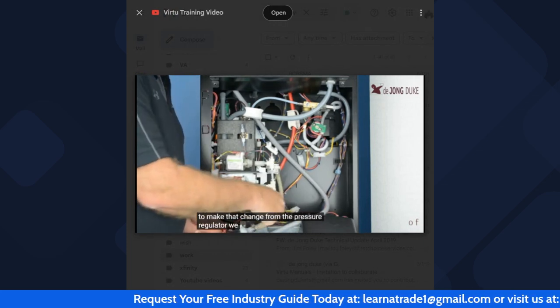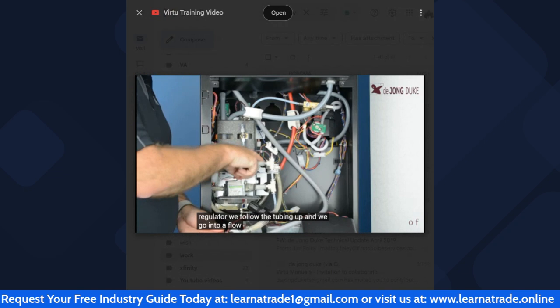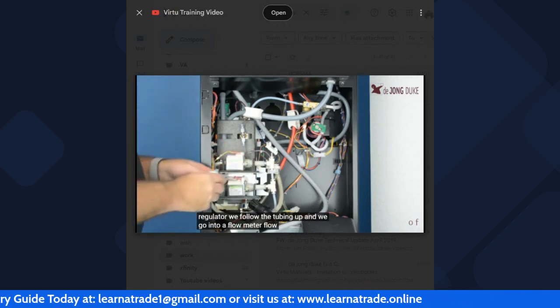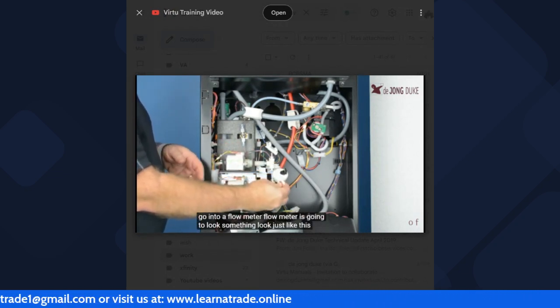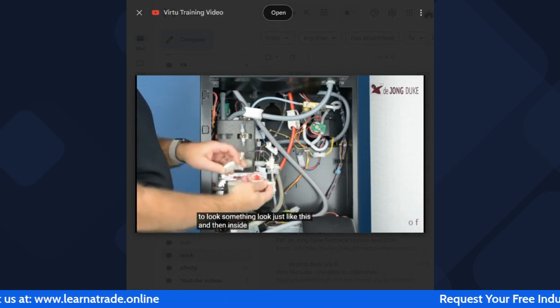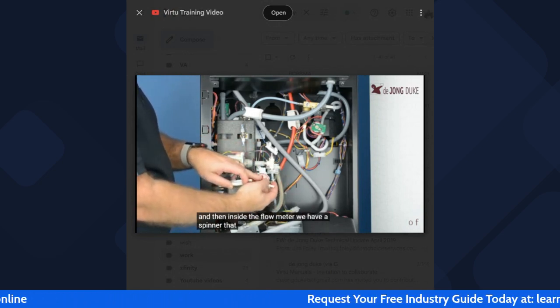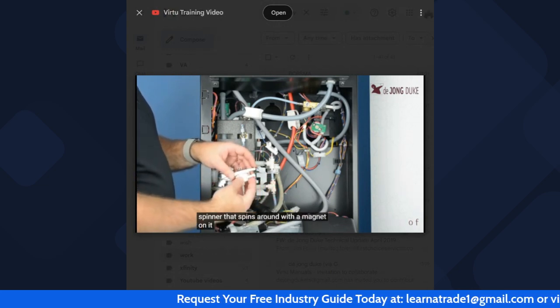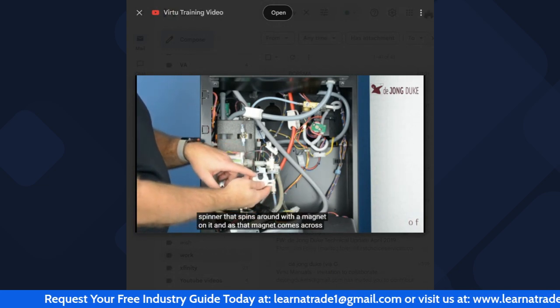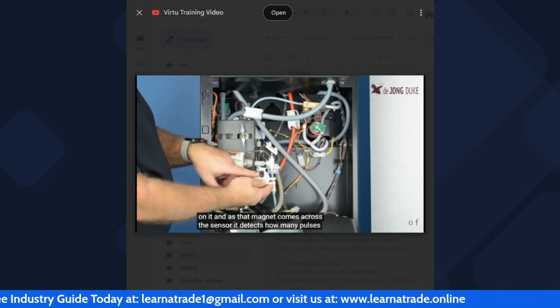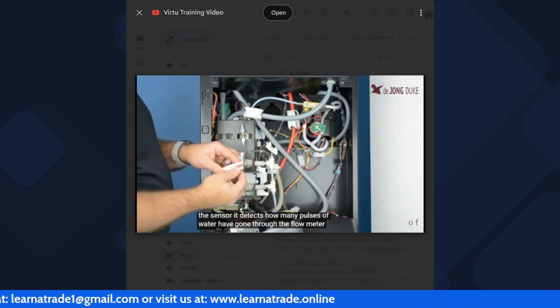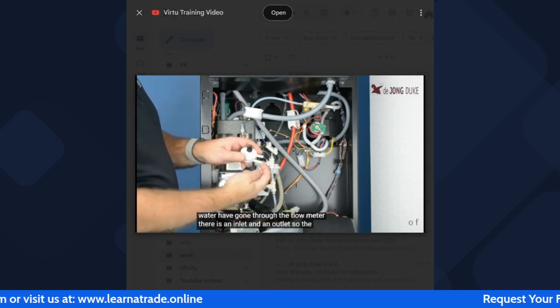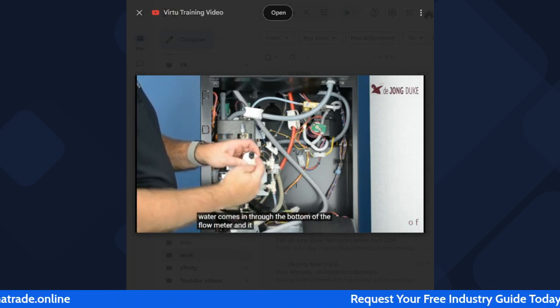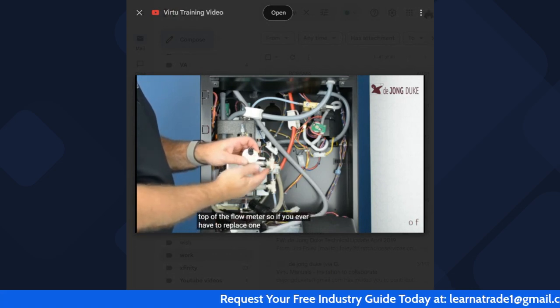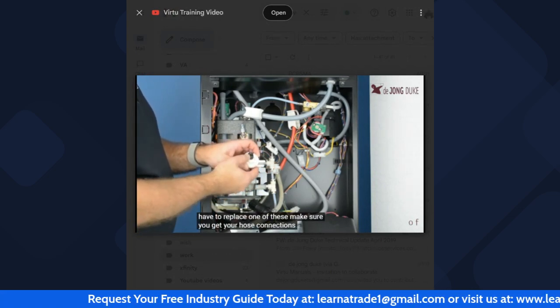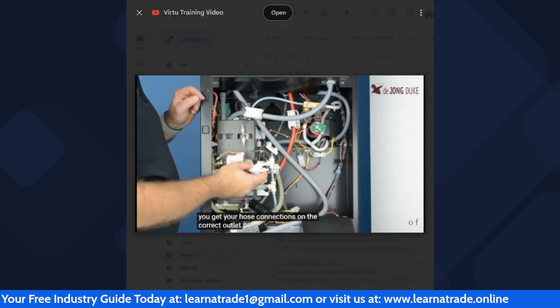From the pressure regulator, we follow the tubing up and we go into a flow meter. Flow meter is going to look just like this. And inside the flow meter, we have a spinner that spins around with a magnet on it. And as that magnet comes across the sensor, it detects how many pulses of water have gone through the flow meter. There is an inlet and an outlet, so the water comes in through the bottom of the flow meter and it goes out through the top of the flow meter. So if you ever have to replace one of these, make sure you get your hose connections on the correct outlet or inlet.